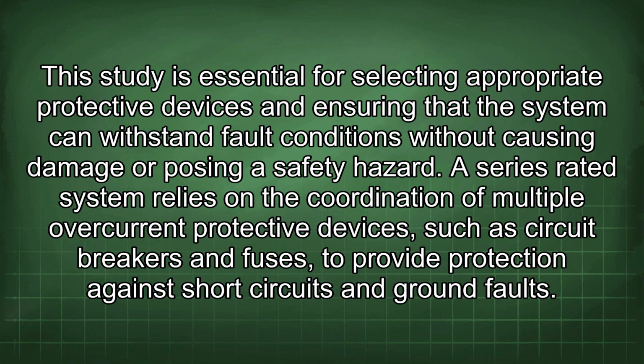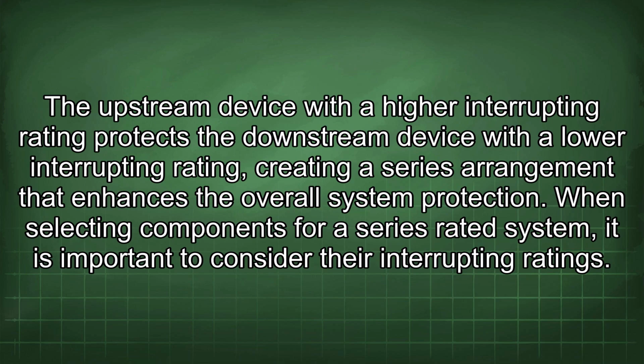A series-rated system relies on the coordination of multiple overcurrent protective devices, such as circuit breakers and fuses, to provide protection against short circuits and ground faults. The upstream device with a higher interrupting rating protects the downstream device with a lower interrupting rating, creating a series arrangement that enhances the overall system protection.